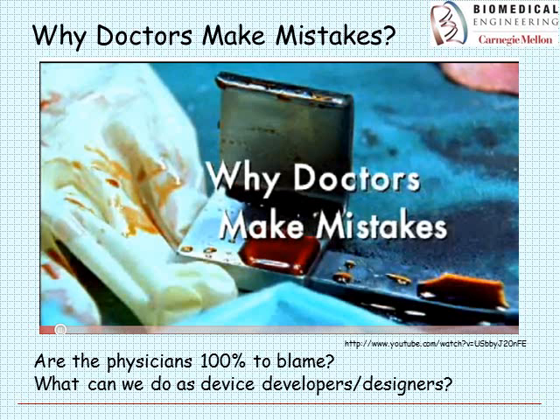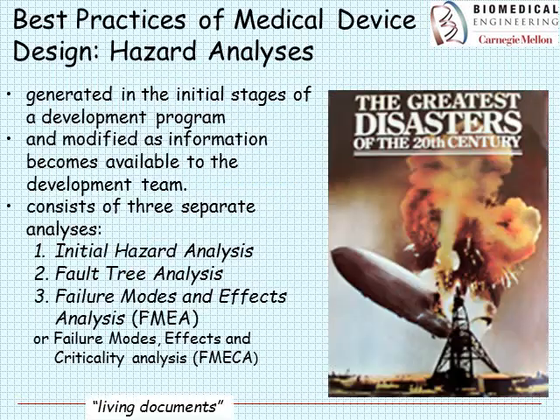We need to take into account that our inventions and devices are going to be used with human beings who are fallible. It's not entirely their fault when an error or accident occurs. As inventors, we can make devices less likely to be misused. This isn't just a good idea — it's actually the law. The Food and Drug Administration requires device manufacturers to have a formal hazard analysis in place.